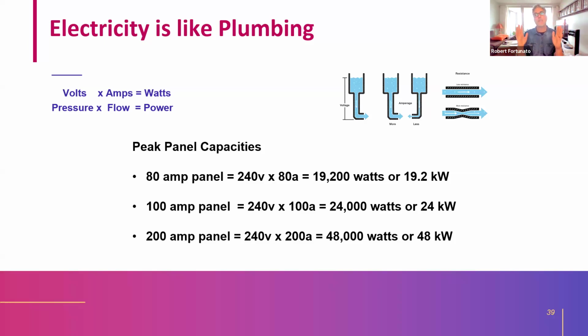That is the maximum peak load that your house can do. If it's asked to do any more than that, the main breaker will break and the house will shut down. The electricity to the house will shut down. Same thing for 100 amp service, the maximum you could have at peak load. And what I mean by peak load is every single thing you have on is on at the same time, then you could not exceed 24 kilowatts. That pressure and that flow could not exceed that.